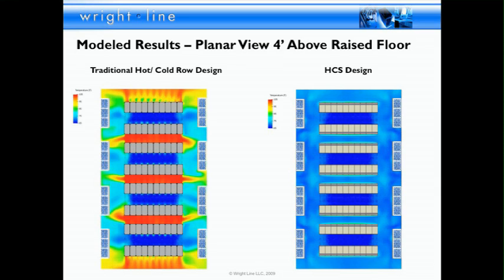Over here on the HCS design, I've actually shut 3 off. And I'm starving the IT equipment by 3%. If the IT equipment's asking for about 89,000 CFM, I'm giving it somewhere in the order of 85,000 CFM. So I'm starving the IT equipment, and I'm still able to maintain inlet temperatures, not exceeding any inlet rack temperatures.